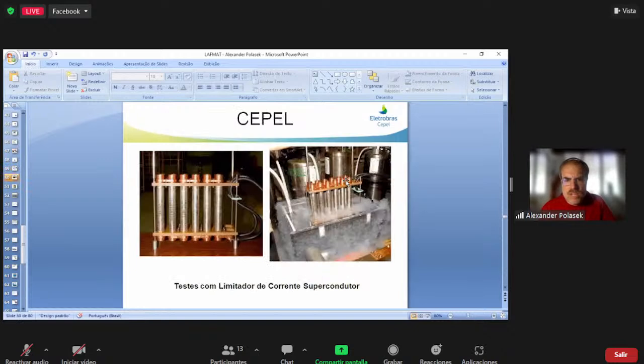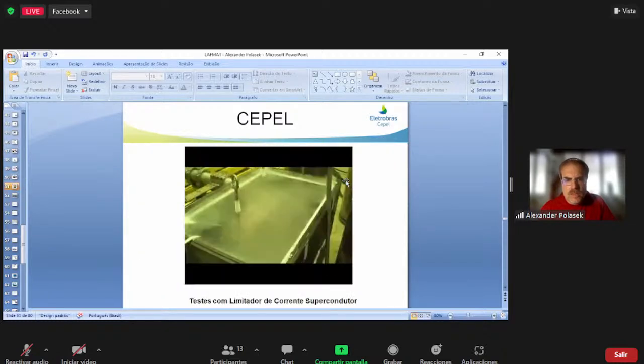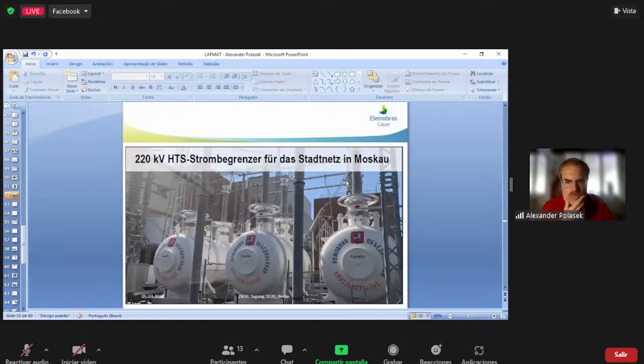These were some tests we did at CEPEL with some bulk components. Also, we did it with tapes, limiting fault currents in liquid nitrogen. This is one of the biggest fault current limiters that exist in the world. There is one in China of this size, one or two in China of this size, and this one in Russia, in Moscow, 220 kilovolts. And you can see here the three cryostats. Each phase is inserted in one cryostat.